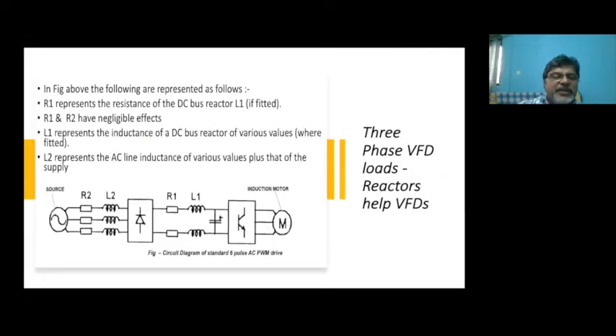As you can see here, you have a variable frequency drive, which is shown by a diode and an inverter, and there is a motor. By installing a line reactor, you can see L2, that's a line reactor, you can reduce the harmonic currents produced by the VFD, because a reactor always works as an opposing force at higher frequency. As you know, inductive reactance is 2πfL, so the higher the harmonics, the higher the impedance. So the reason why you put reactors at the input of a drive is to reduce the effect of harmonics.